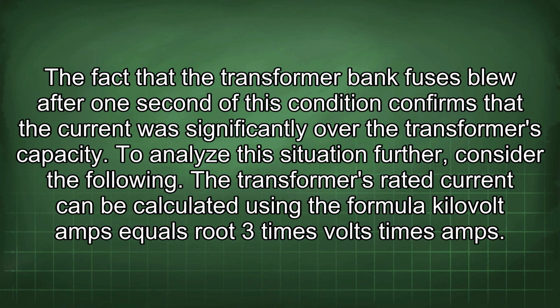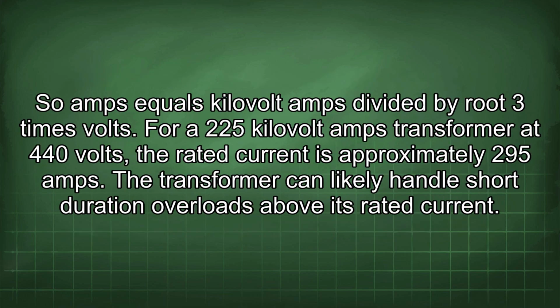The fact that the transformer bank fuses blew after 1 second of this condition confirms that the current was significantly over the transformer's capacity. To analyze the situation further, consider the following. The transformer's rated current can be calculated using the formula kilovolt amps equals root 3 times volts times amps. So amps equals kilovolt amps divided by root 3 times volts. For a 225 kilovolt amps transformer at 440 volts, the rated current is approximately 295 amps.